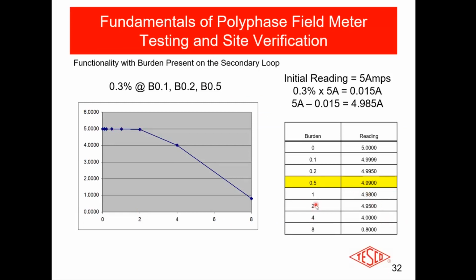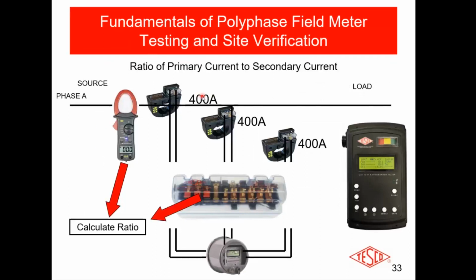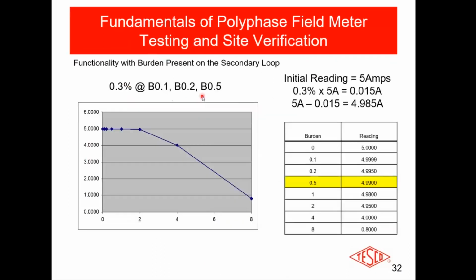But as you get an increasing amount of burden on there, my accuracy goes way off to the point where it's kind of useless, all right? So you really want to keep this particular setup at less than half an ohm of burden. Well, how do we get burden in a setup? We're going to talk about that, and that's part of site verification. But you can get it from loose connections. You can get it from corrosion. You can get it from setting the CTs too far away from the meter. We talked about ideally wanting to keep them as close as possible.